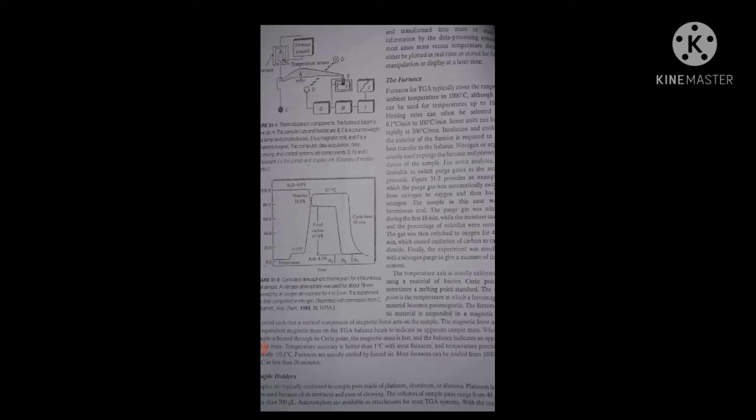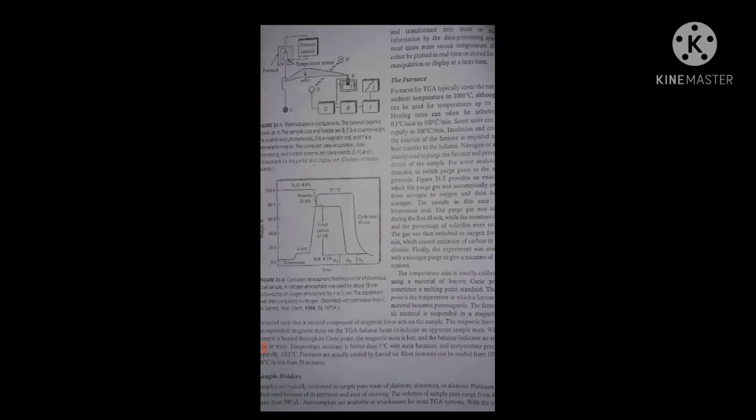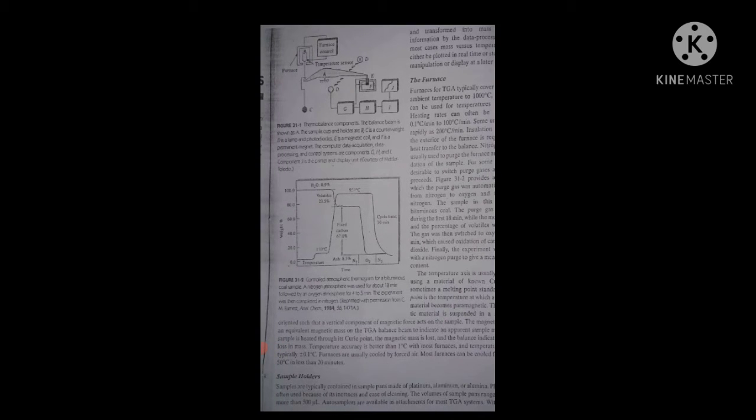The volume of the sample ranges from 40 microliters to 500 microliters. Auto samplers are also available as attachments for most TGA systems. With the majority of these units, all aspects are automated under software control. The sample pan loading and weighing, the furnace heating and cooling, and the pan unloading are totally automatic.